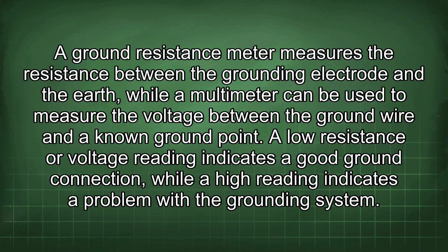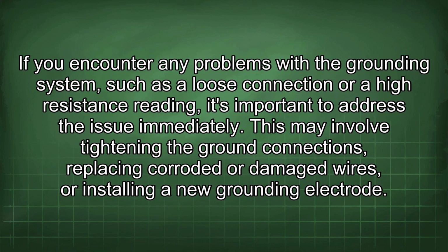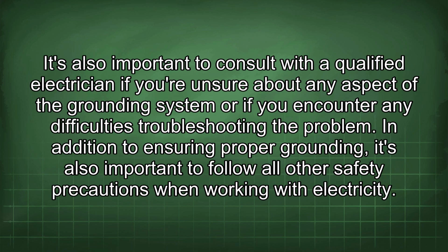grounding system. If you encounter any problems with the grounding system, such as a loose connection or a high resistance reading, it's important to address the issue immediately. This may involve tightening the ground connections, replacing corroded or damaged wires, or installing a new grounding electrode. It's also important to consult with a qualified electrician if you're unsure about any aspect of the grounding system or if you encounter any difficulties troubleshooting the problem.